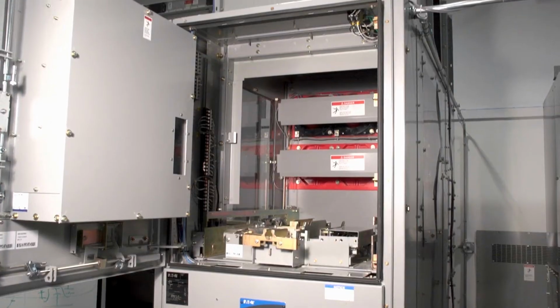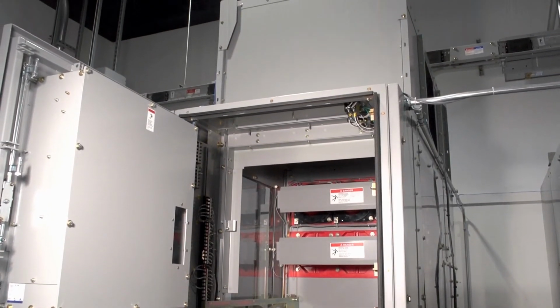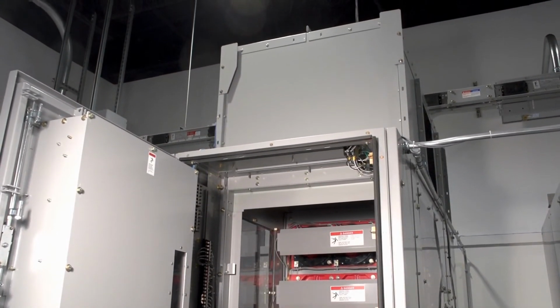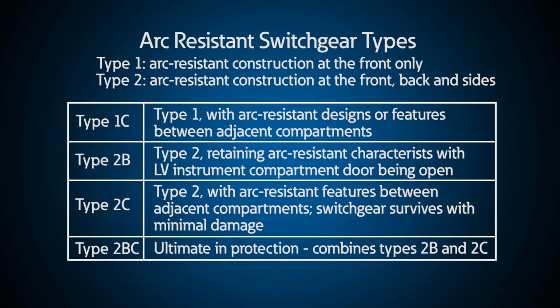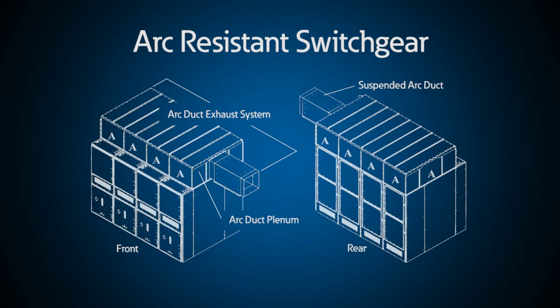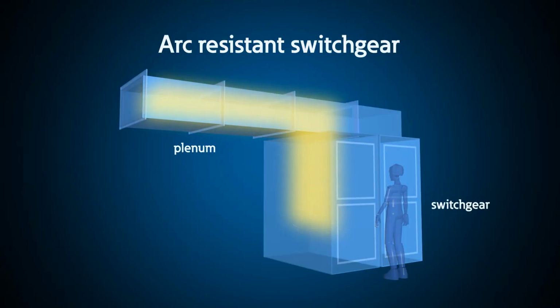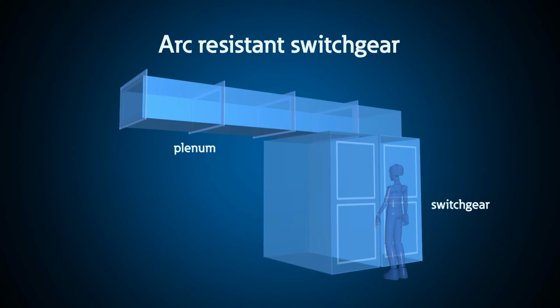Now, switching gears a little bit, let's talk about arc flash solutions that keep people out of harm's way. The first solution is called arc-resistant switchgear. In general, arc-resistant equipment contains and redirects arc energy away from personnel out of the top of the equipment. The most common is called Type 2B, meaning you could walk all the way around a section of equipment, and if an arc flash occurred inside, you wouldn't be hurt because the arc flash energy would be exhausted or dissipated out the top, and in some cases through a plenum outside the room or area where you're working.